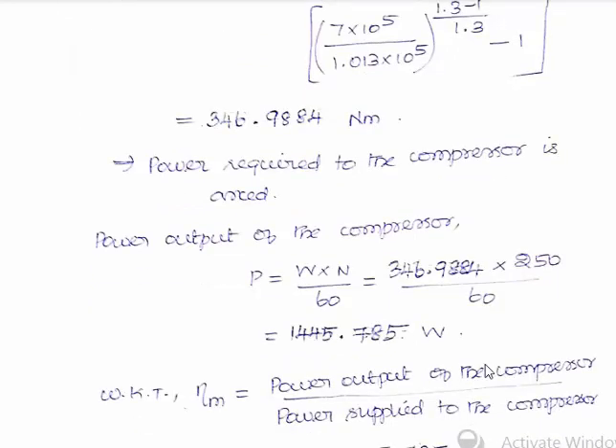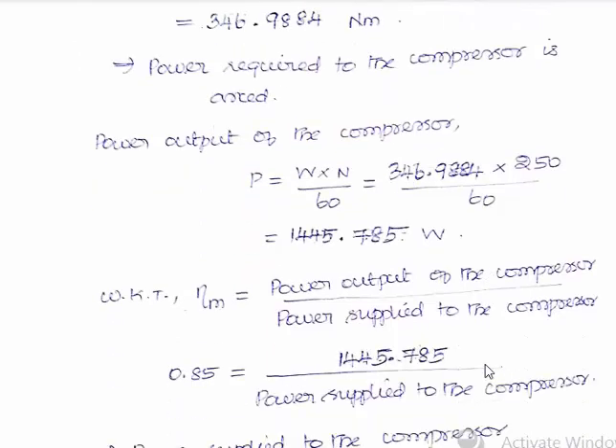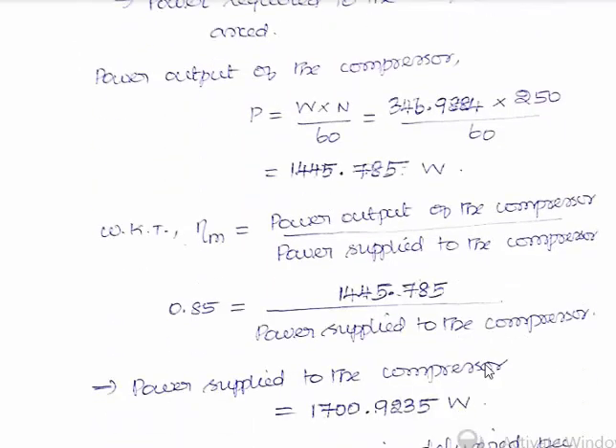Using the mechanical efficiency formula: mechanical efficiency = power output / power supplied to the compressor. The power output from the previous step is 1445.785 W, and mechanical efficiency is 85%. Substituting, the power supplied to the compressor is 1700.9235 W.